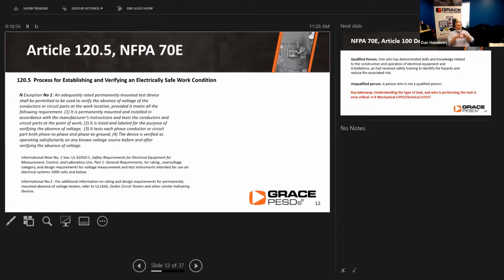And this exception really talks about the process of doing lockout tagout procedures, and basically you have UL 61010-1, which talks about the safety requirements for electrical equipment for measurement, control, and laboratory use. General requirements for the rating over voltage category, and then the design requirements for voltage measurement and test instruments intended for use on electrical systems 1,000 volts and below. So what they do is UL tests the equipment, verifies that it operates properly and that it passes their requirements for that level.